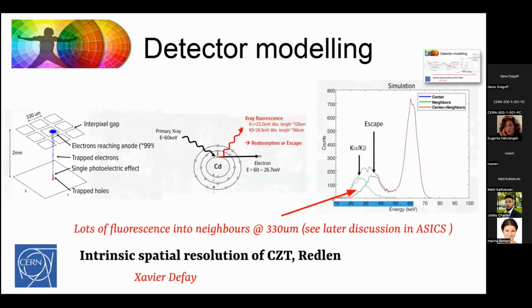Redlen then talked about some of the problems in these semiconductors, and this is something that's going to come up a bit later on when I start talking about the new detectors that are coming out. If you have a crystal like this, say 2 millimeters thick and 300 micron pixels, you get an interaction. The photon comes down, interacts, and produces a charge cloud, and that drifts. But worse than that, some of these things, they'll hit a cadmium atom and you'll get fluorescence, K alpha and K beta, and they can come out symmetrically around the atom, and they'll travel a really long way, up to 128, 168 micron through. And so if you've got pixels that are 300 micron, a third of a millimeter, this green line is how much of that charge or how much of that photon energy ends up being deposited in the neighbor, and that ruins your spectrum. Ideally, when you're measuring a spectrum, if you put in a 60 keV beam, you want to measure 60 keV. Whereas here, they put in a 60 keV beam and you start measuring photons much lower down. And so compensating for that has been a real challenge, and I'll talk more about that later.